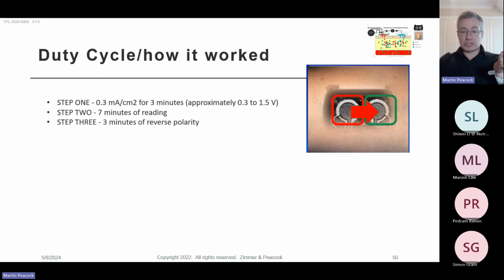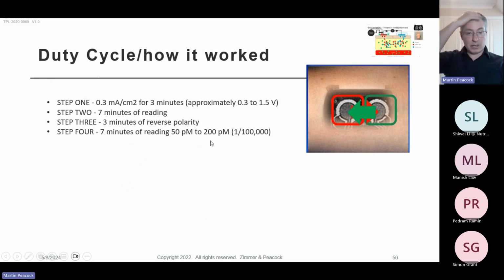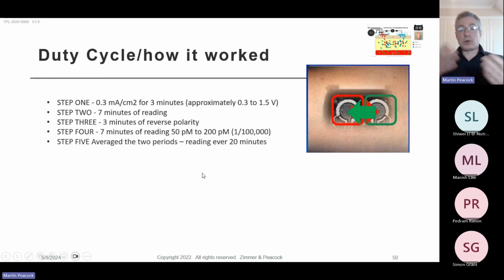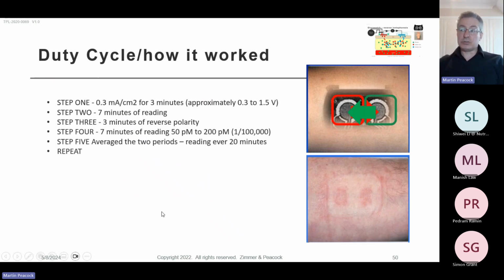So they basically had two glucose sensors on there. They would extract and read, and then they would reverse the voltage and extract and read on the other one. And I think they were extracting glucose in the concentration of 50 picomolar to 200 picomolar. Anyone who's working with blood knows that it's in the millimolar. So they were really not extracting that much material. And that's probably why they had 7 minutes worth of averaging of that particular signal. They would extract and read, extract and read, and they'd end up averaging the two signals.